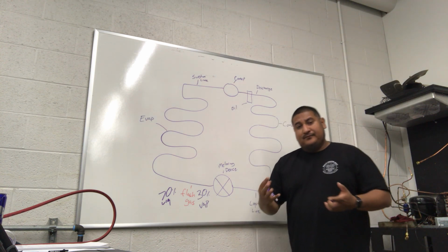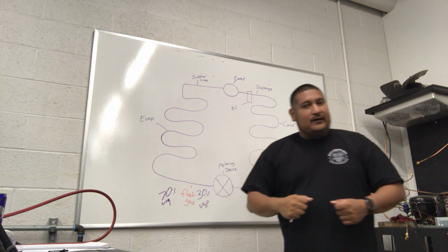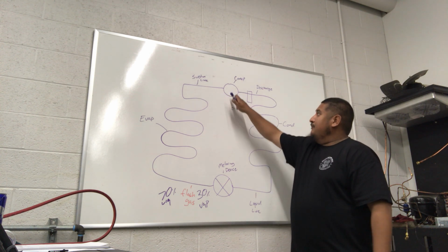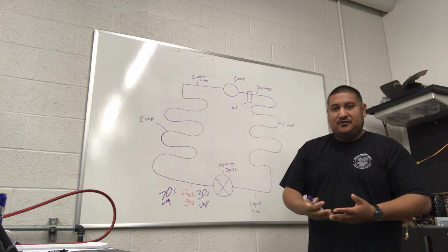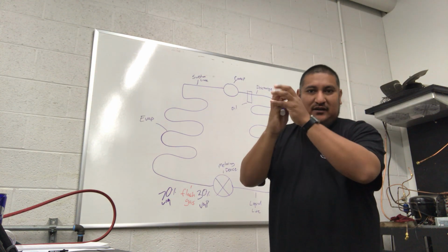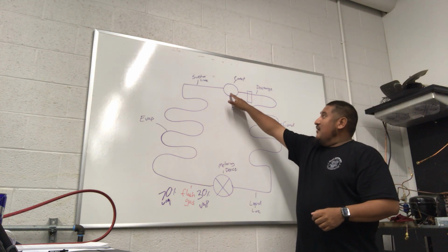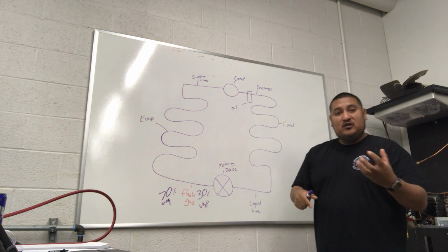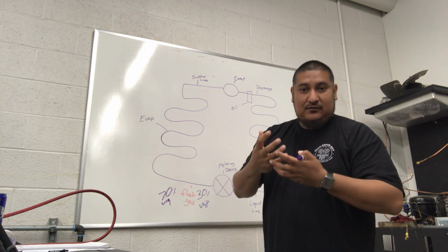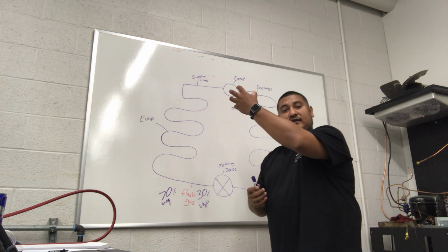Oil and refrigerant, they get along, but not that great, right? Now what I mean by that is that oil, think of it like 16-year-olds, right? That oil and the refrigerant, they want to mix and they want to bond and they want to get together, right? Well, what's going to happen is this compressor is going to be running a little bit warm, a little bit hot, right? So the refrigerant naturally is going to try to boil off if there's any liquid in there. When it boils off, it's going to try and take that little oil with it, right?